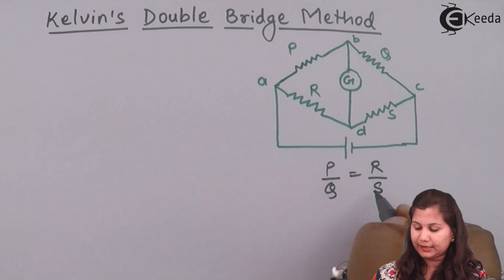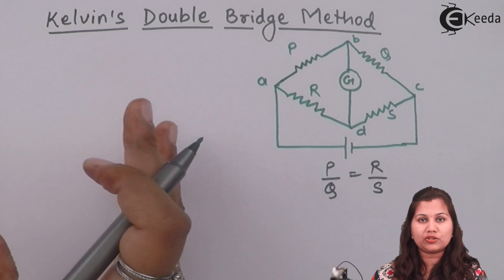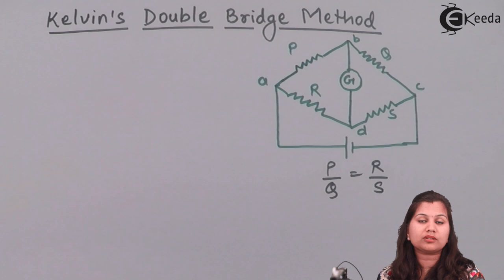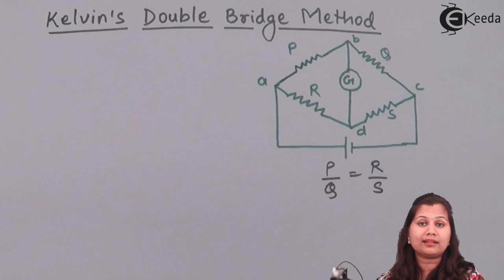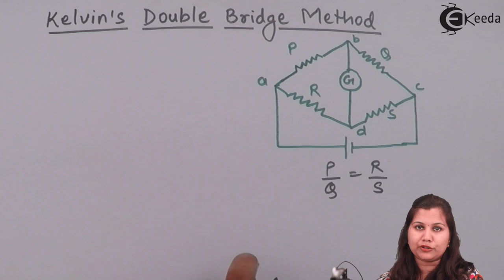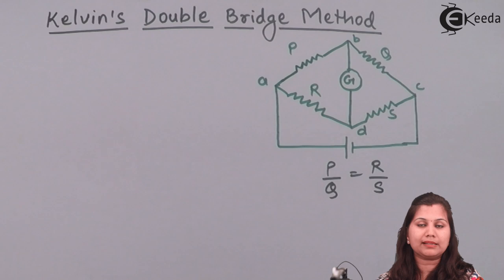The Kelvin double bridge is a modification of the Wheatstone bridge because the Wheatstone bridge can measure resistances from a few ohms to several mega ohms. But if we want to measure resistances which are very low — under 1 ohm — then we use the Kelvin double bridge, which requires some modifications to the Wheatstone bridge.